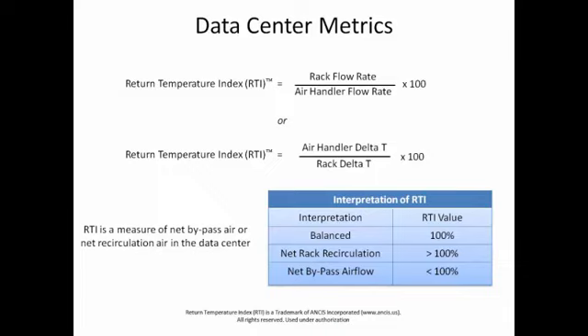The other case is not as good either. If your rack flow rate is higher than your air handler rate, this thing goes above 100%. You can see here. Now that problem is you don't have enough air coming from the air handlers, and as a result, the rack is breathing its own exhaust back around in a loop. So both of those are undesirable. You want this thing balanced.